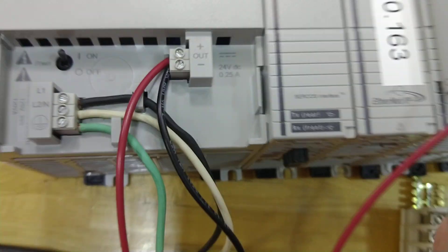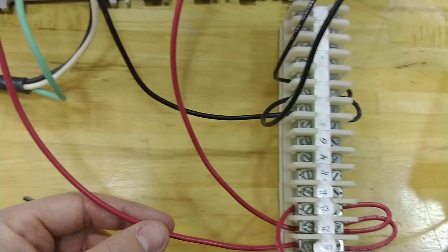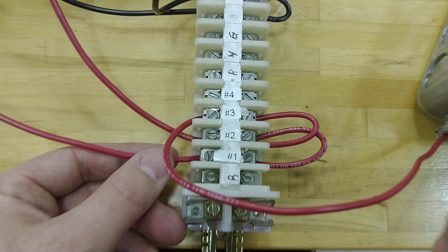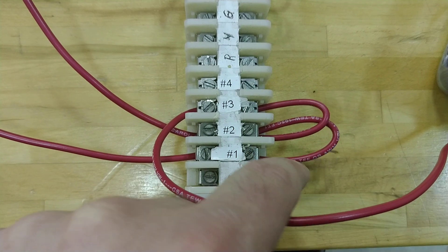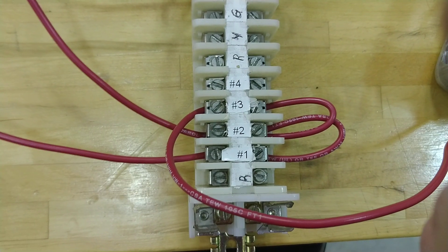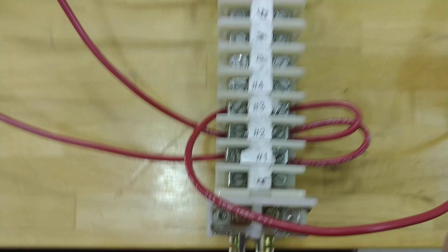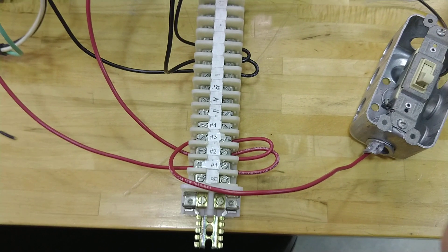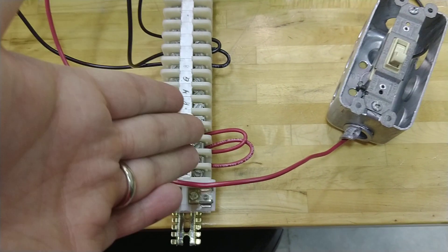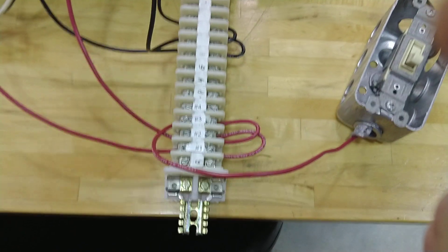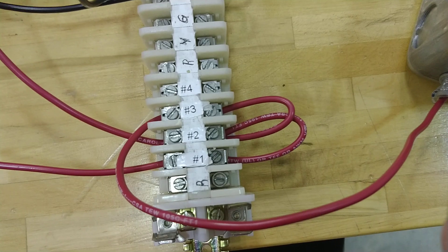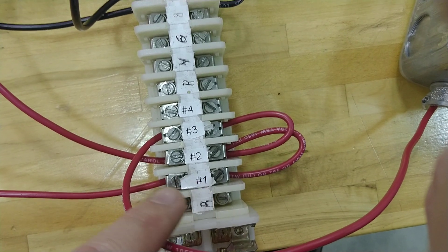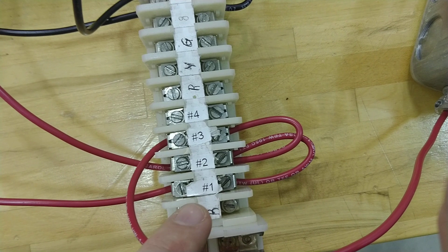I have taken this red line and run it to basically a terminal block with jumpers tying everything together electrically. Anything that I need in industry, typically. Now, this is not pretty. This is really classroom, because in reality I would have jumper blocks that would go in, but this will give you the idea. Instead of using wire nuts like you would in residential, I just tied in all my DC power supply into here.